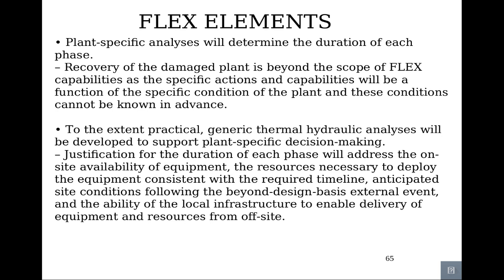Plant-specific analysis will determine the duration of each phase. Recovery of the damaged plant is beyond the scope of FLEX capabilities, as the specific actions and capabilities will be a function of the specific condition of the plant, and these conditions cannot be known in advance. To the extent practical, generic thermal hydraulic analysis will be developed to support plant-specific decision-making. Justification for the duration of each phase will address the on-site availability of equipment, the resources necessary to deploy the equipment consistent with the required timeline, anticipated site conditions following the beyond-design-basis external event, and the ability of the local infrastructure to enable delivery of equipment and resources from off-site.